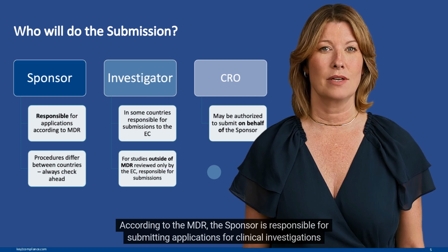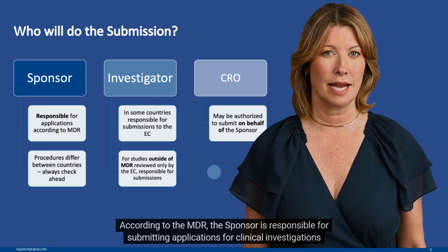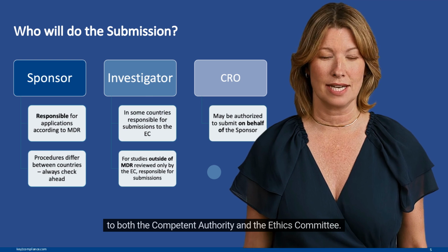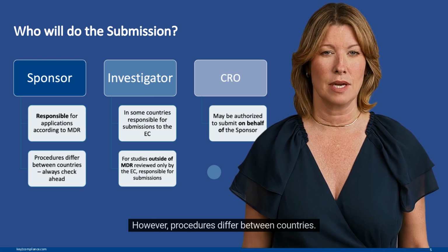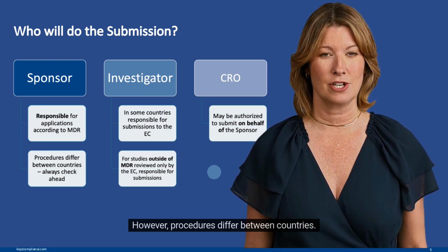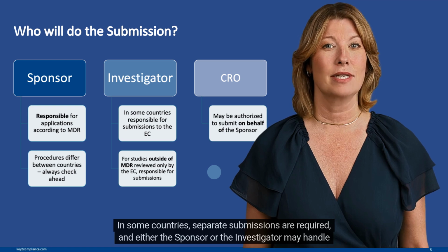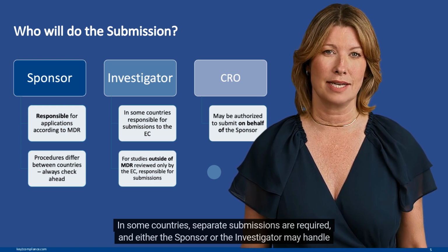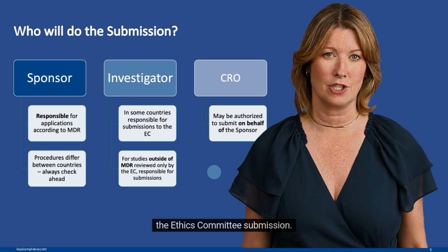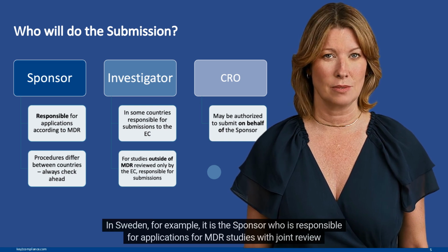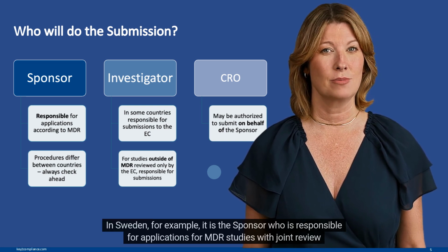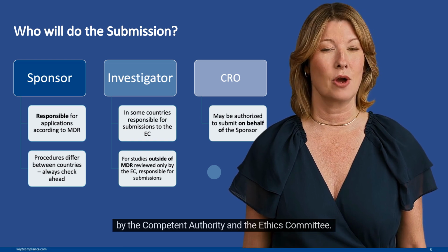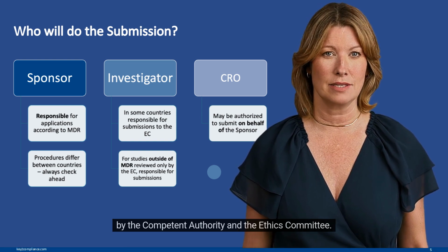According to the MDR, the sponsor is responsible for submitting applications for clinical investigations to both the competent authority and the Ethics Committee. However, procedures differ between countries. In some countries, separate submissions are required, and either the sponsor or the investigator may handle the Ethics Committee submission. In Sweden, for example, it is the sponsor who is responsible for applications for MDR studies with joint review by the competent authority and the Ethics Committee.